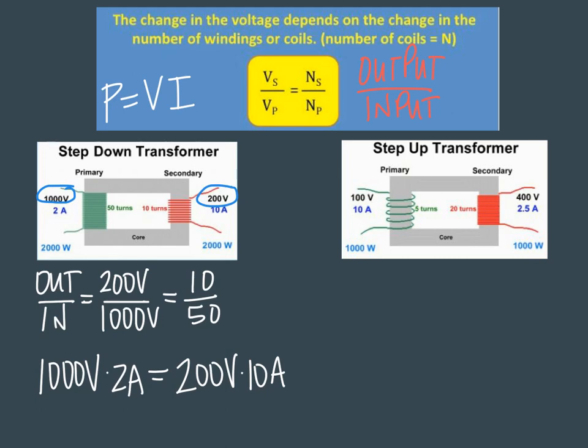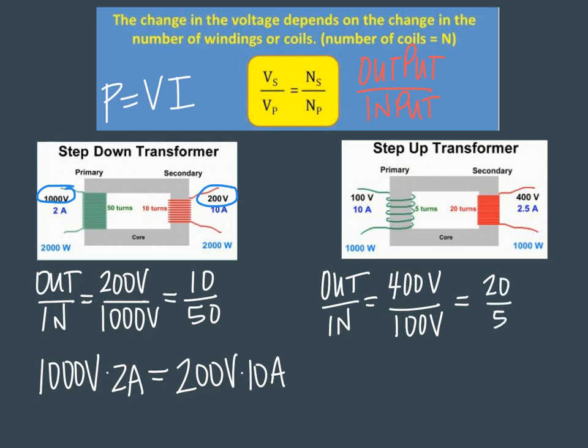If we look at a step-up transformer, on the secondary side there are 400 volts across the wires versus only 100 on the primary side. Looking at the turns, we see that same 4:1 ratio, 20 turns versus 5 turns. But again, in terms of power, 100 volts times 10 amps, or 1000 watts, is the same as 400 volts times 2.5 amps, again 1000 watts.